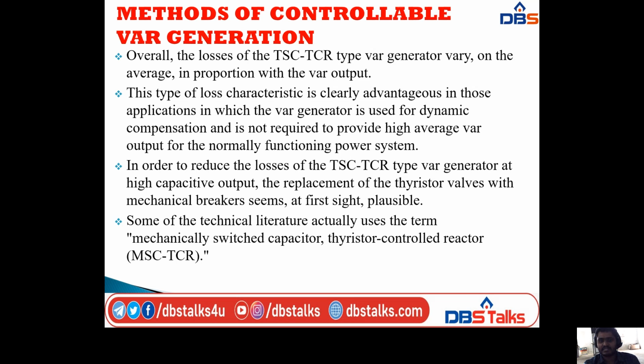So this type of loss characteristic is clearly advantageous in those applications in which the VAR generator is used for dynamic compensation and is not required to provide high average VAR output for the normally functioning power system. Okay, so if you want to reduce the losses of the TSC-TCR VAR generator at a high capacitive output, the replacement of the thyristor valves by mechanical breakers seems at first sight plausible.